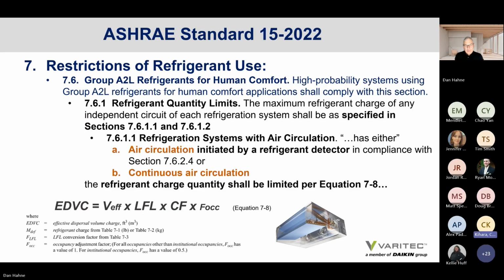So in the past, we were using A1 refrigerant, and that was using RCL, right? So that had the 26 pounds per 1,000 cubic feet, RCL. So now that we're using LFL because of the flammability limits, right? We need to use that 4.8 pounds per 1,000 cubic feet. Does that make sense to everybody? Because we're using A2Ls now, there's a flammability aspect to it. Correct. So it's kind of used interchangeably in a sense, because we have to take into account the flammability aspect of it.